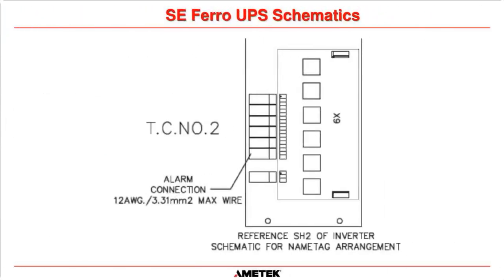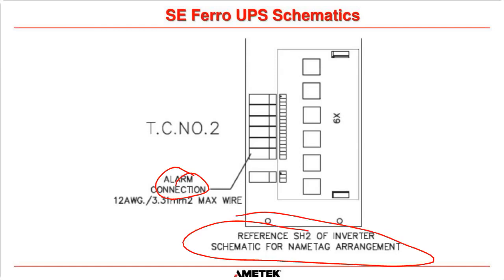And then the last thing on that second page of the outline was the alarm relays. Basically it says alarm connection here, and it says reference sheet 2 of the inverter schematic for name tag arrangement. So there's a name tag on each of these connections, and this is normally closed, normally open, common connection. So 3 connections for each tag. And depending on how many alarms you bought from us at the time you purchased the UPS will depend on how many alarm boards you have and how many connections you would have.